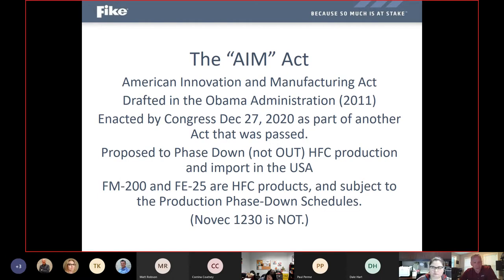And when we talk about FM200 and Ecaro 25, they are considered HFC products. Even though they've been relatively ignored for the past many years as all these environmental discussions and focus took place, or they're recognized that when they are released to the atmosphere, they're actually doing more good than harm because they're actively putting out a fire. Ultimately, they are still HFCs, and the AIM Act was put in very bluntly to say anything that's an HFC, regardless of what it is or how good it is or its benefits, if it's still considered an HFC, it's going to be part of the phase down schedule we're now looking to implement.